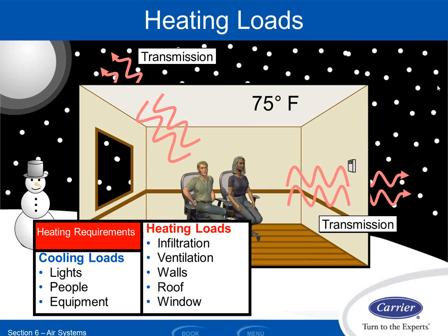And in reality, that is true. I do get that free heat in the wintertime from the sun. However, the time that I'm designing the equipment for, the time of year is, whatever, January at some very late time, 2 a.m. or something like that, when it's the absolute coldest outside. And at that point in time, the sun is not up, right? So I don't get a credit for sun in terms of designing my system.